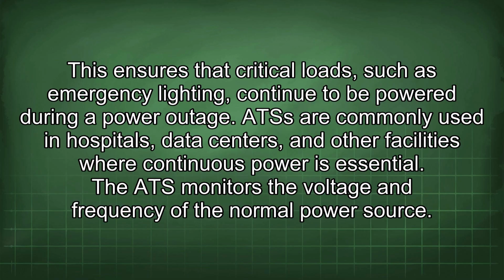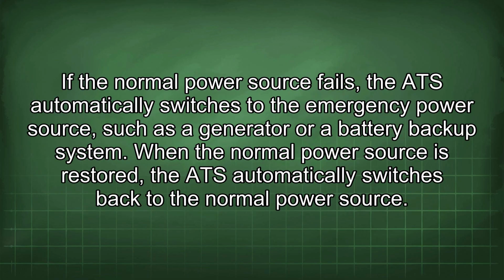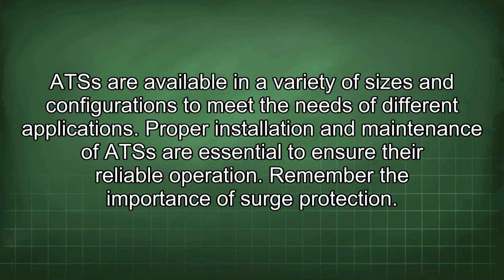The ATS monitors the voltage and frequency of the normal power source. If the normal power source fails, the ATS automatically switches to the emergency power source, such as a generator or a battery backup system. When the normal power source is restored, the ATS automatically switches back to the normal power source. ATS are available in a variety of sizes and configurations to meet the needs of different applications. Proper installation and maintenance of ATS are essential to ensure their reliable operation.